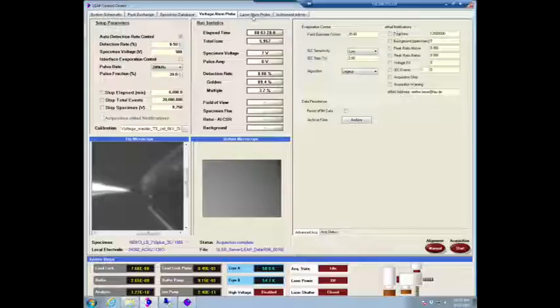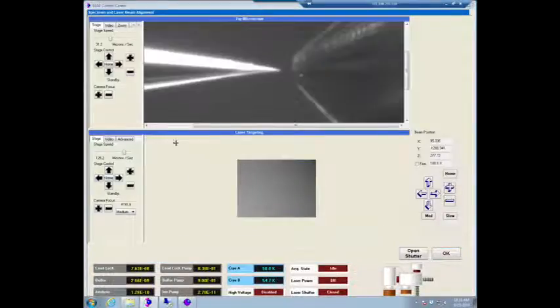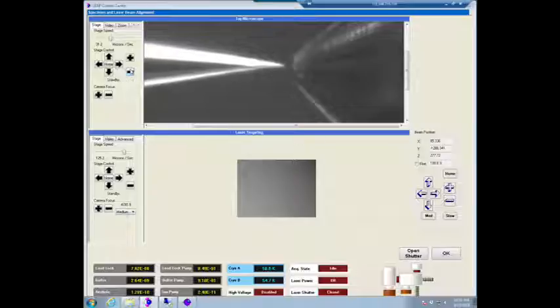Okay, this is okay. Usually, if you look at a LEAP sample, you can usually tell if it's a good sample or a bad sample. You can't see the tip physically, but you can usually gauge whether it's a good or a bad atom probe tip, and that one I would actually expect to give us results. So I might just give it a try if we can move it in and out.